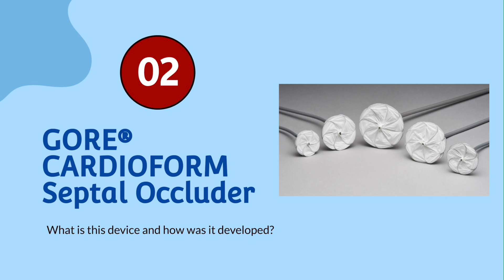In order to eliminate the possibility of nickel poisoning or allergic reactions, this device is made of platinum-filled nitinol wires. This allows for minimal nickel elution and exposure. There are currently 2 devices approved by the FDA for the closure of the foramen ovale. These include the Gore cardioform septal occluder and the Amplatzer PFO occluder. This video shows how a Gore cardioform septal occluder is being placed.